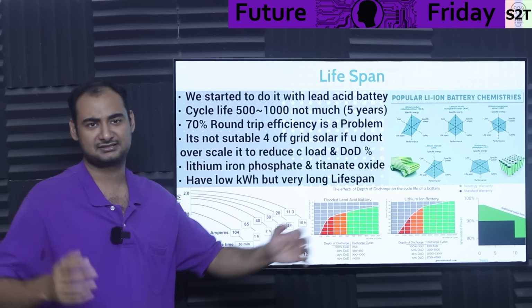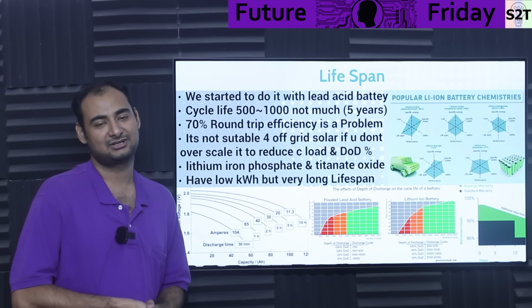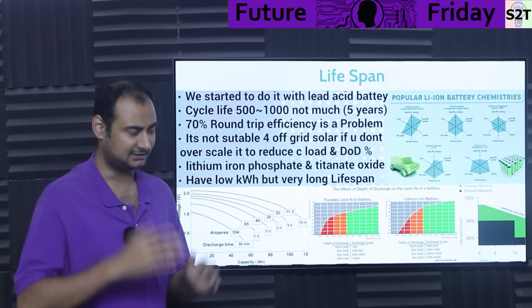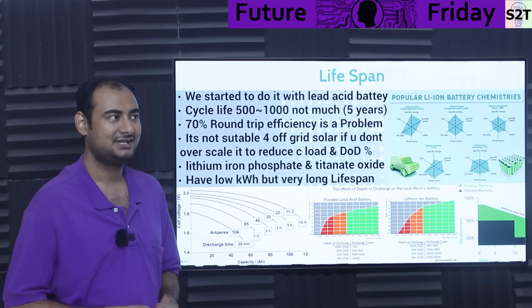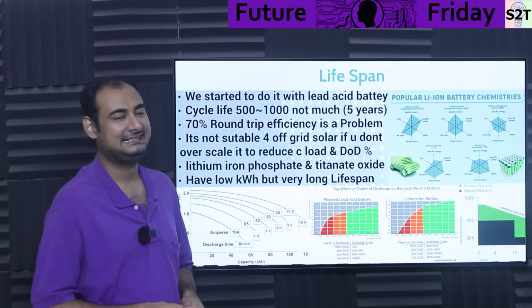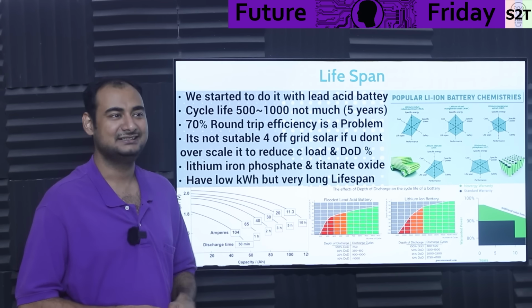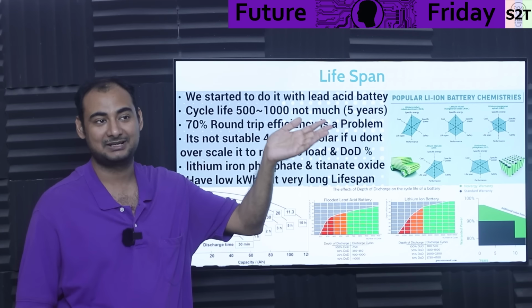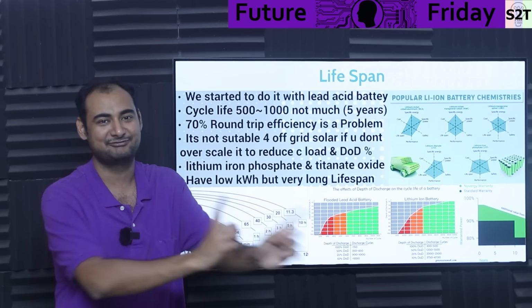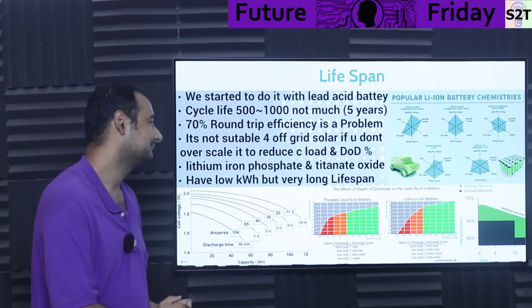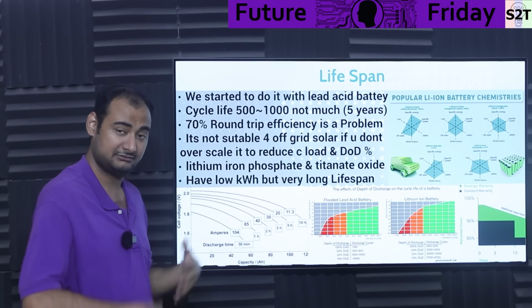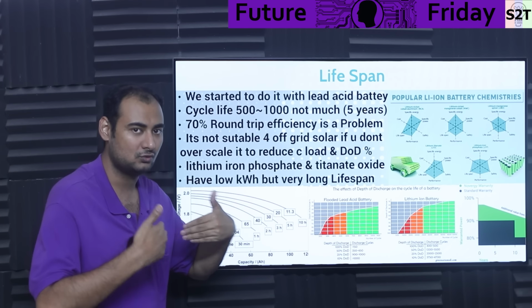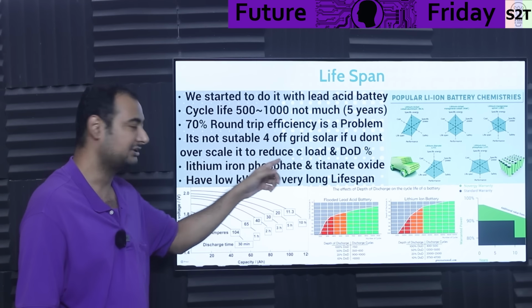If you're making a diesel submarine that needs to run a 1 megawatt motor full bore, you design the battery bank to supply 8 or even 10 megawatts. After 15 years it may only provide less, but at least it still functions. That's why it's not suitable for off-grid use—you can force it, but the penalty is you have to overscale it and reduce the C loading.